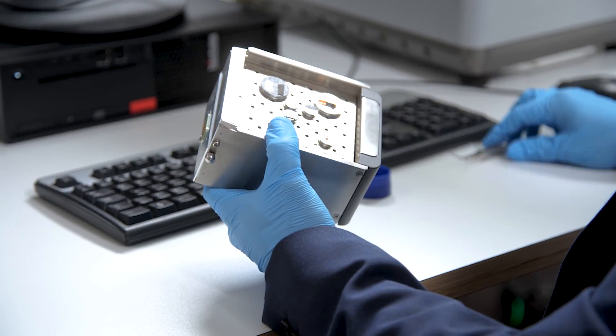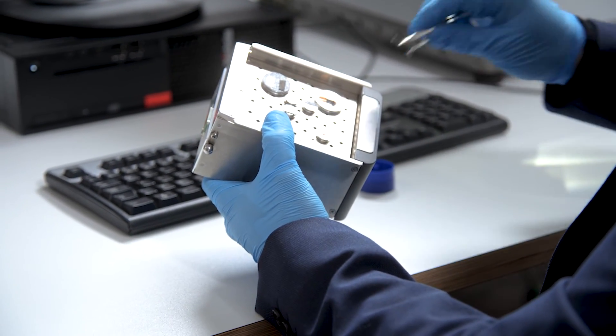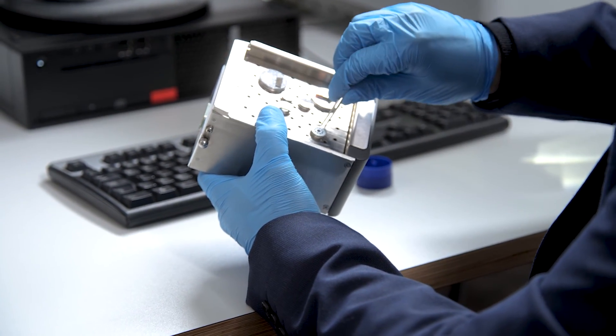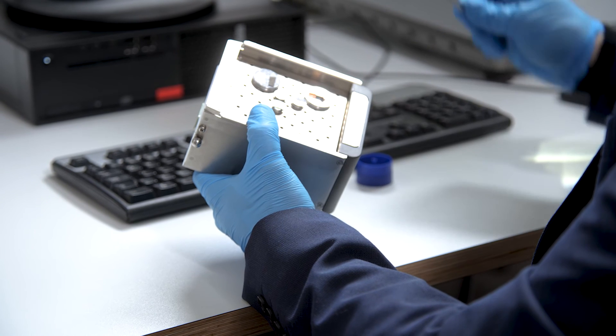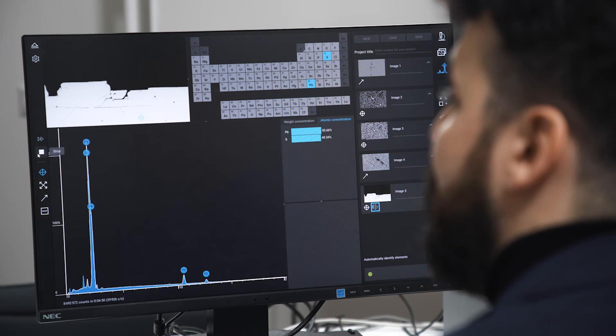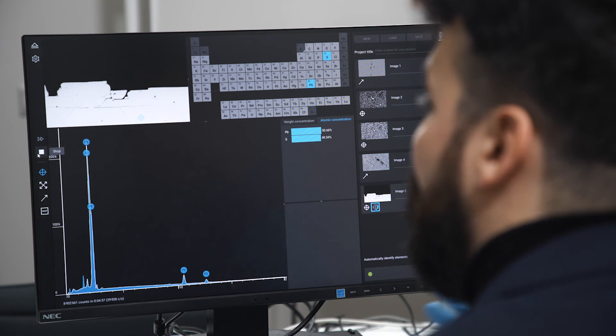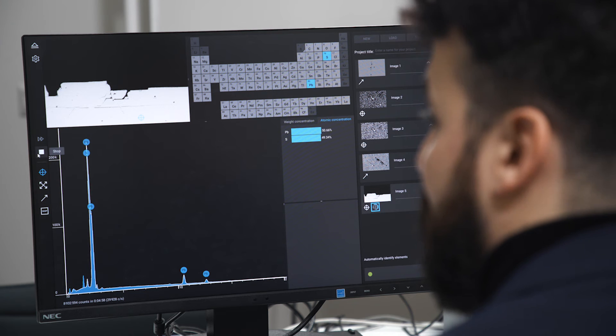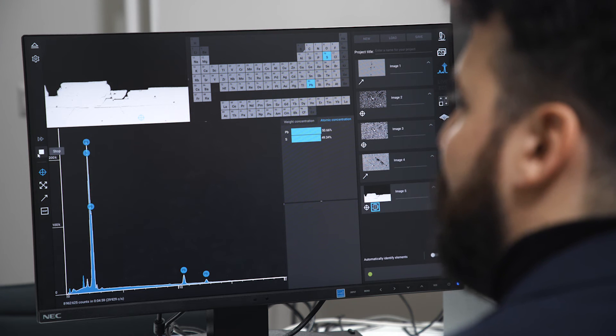This is a good example of how EDS can give you very accurate information no matter what the composition of the sample is. In this example you can see how the quantification is extremely close to the stoichiometric ratio of one to one, which is expected in lead sulfide.